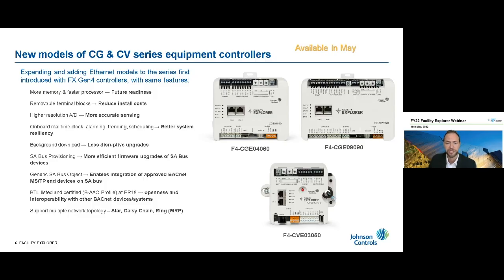And it's worth mentioning that they also support different IP network topologies, such as STAR, which we call home run cables, where every controller gets a separate IP connection and an IP port, or they support daisy chains, so they can be chained together in and out, as well as support ring IP connection or topology through the MRP or the ring manager. So we have 3 new IP models.